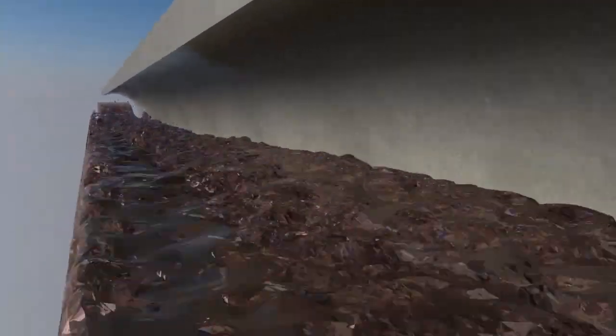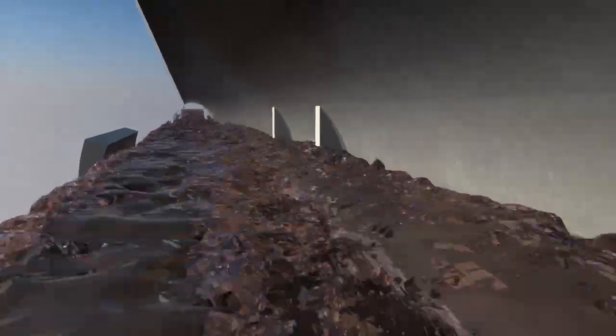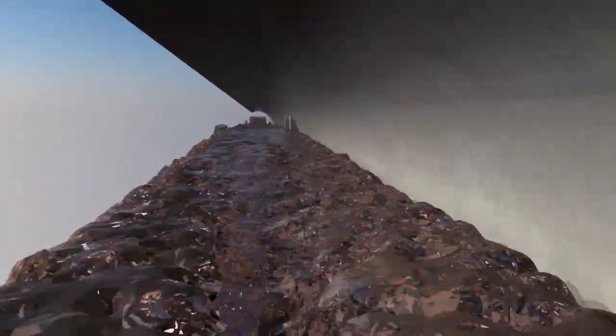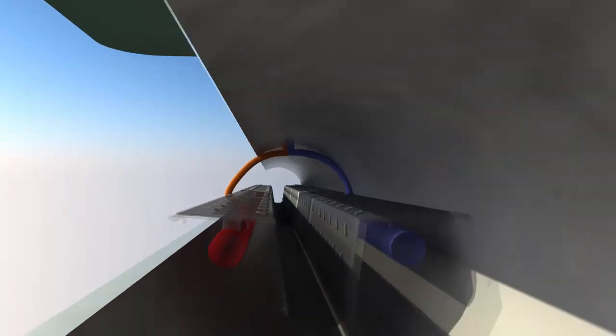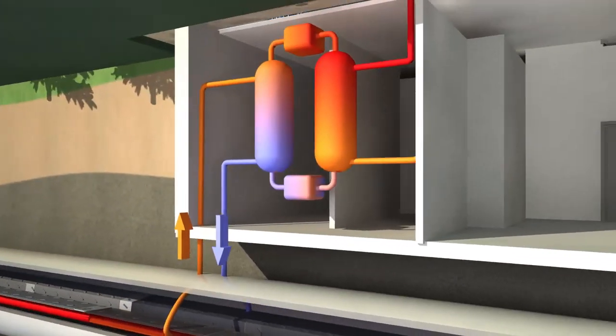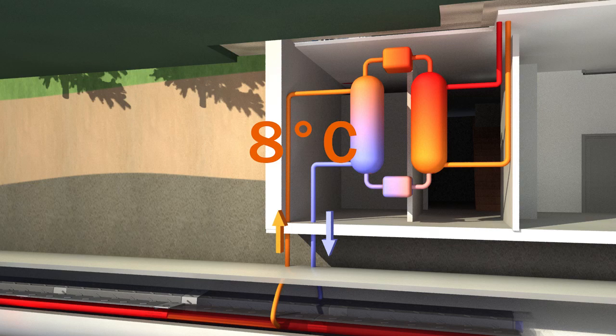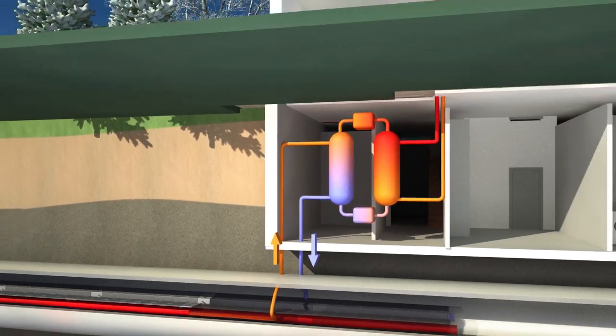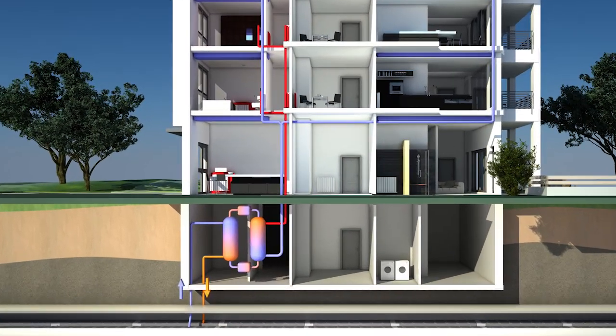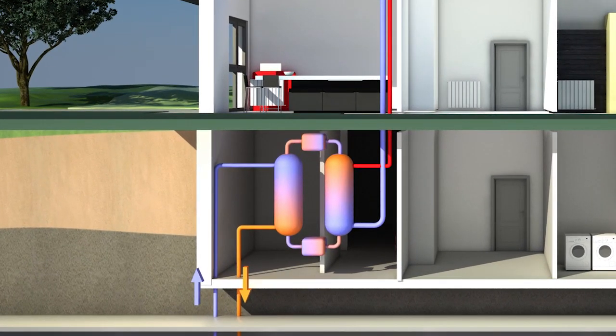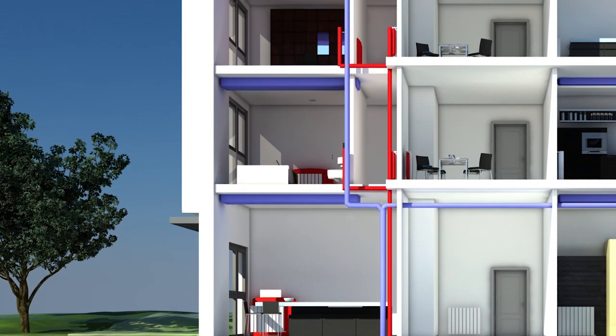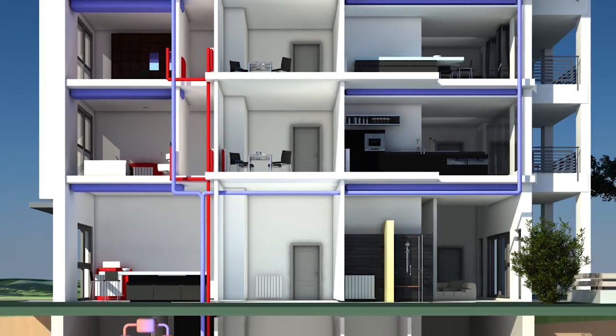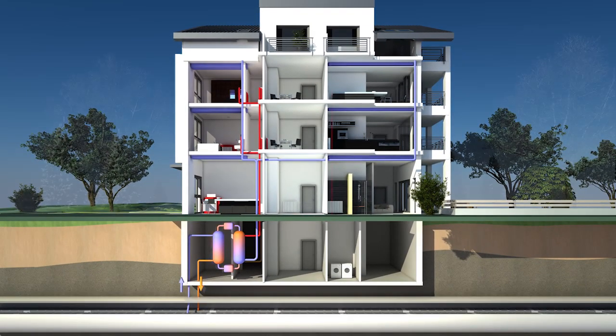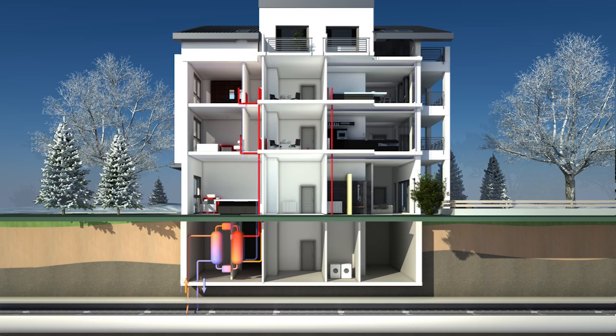The flow of warm wastewater, which is between 10 and 20 degrees Celsius all year round, is discharged into the sewer network via heat exchangers, which transfer this energy to an intermediate cycle. A heat pump pumps the heat to the required energy level and provides it to the final customer. However, heat pumps are not only suitable for heating. During the summer months, they can use the relatively cold flow of wastewater for air conditioning in buildings. Their efficiency is greatly improved through combining heating and cooling.